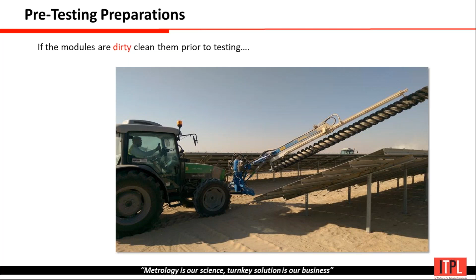Then, low light condition will result in inaccurate measurement. If you are testing a solar panel or a string, it has to be done in good sunlight condition. The radiation level should be minimum 600 or 650 watt per meter square. If it is less than that, we will definitely get values, whether at a radiation of 200 or 300 or 400, but those values will not be authentic enough to justify to the clients or to conclude any final results. So every time we measure, radiation should be at least a minimum of 650 watt per meter square.